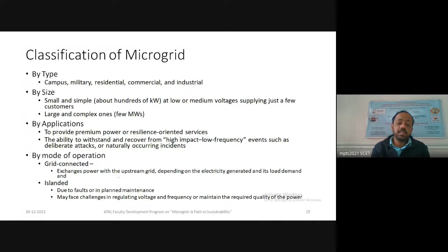By configuration, loads, micro sources, and storage devices are integrated leading to different configurations: AC network microgrids, especially in the area of AC distribution, of which there are three types - single phase, three phase with neutral, and three phase without neutral. Second is the DC network microgrid for emerging DC sources and loads, which could be monopolar, bipolar, homopolar, or hybrid, a blend of AC and DC microgrids.